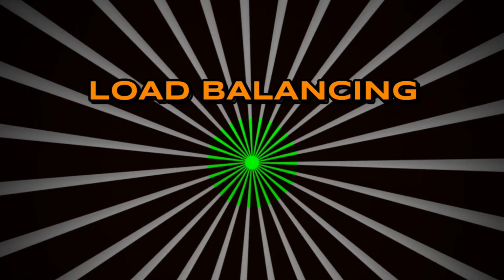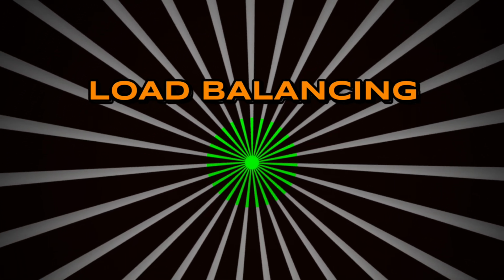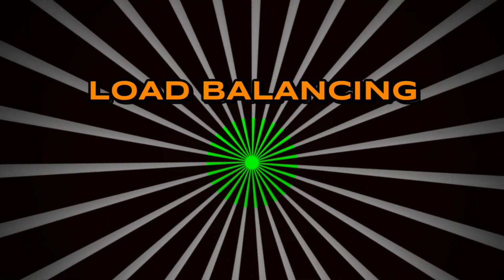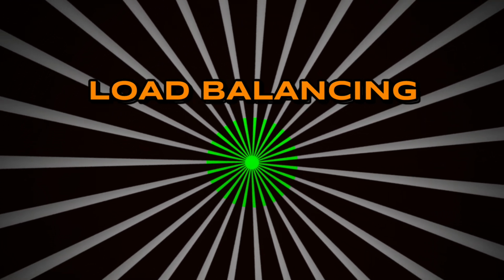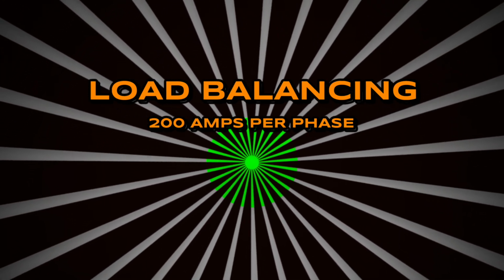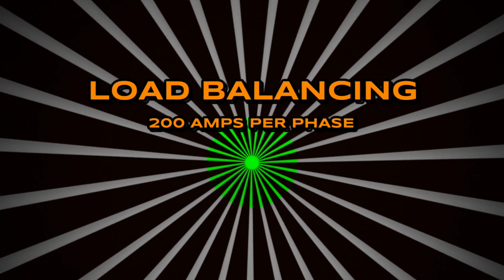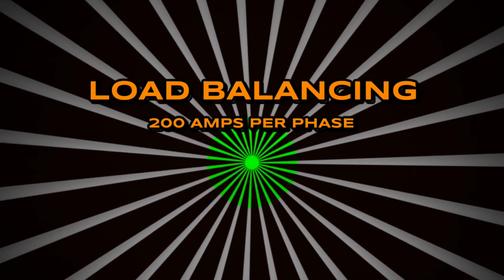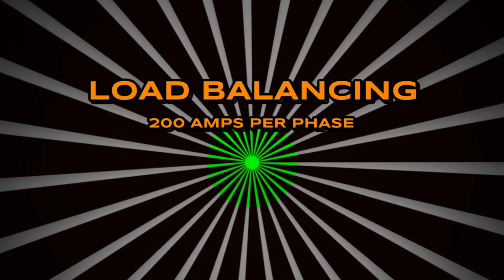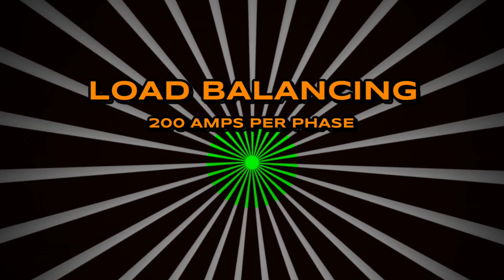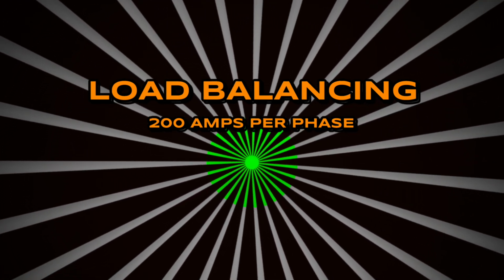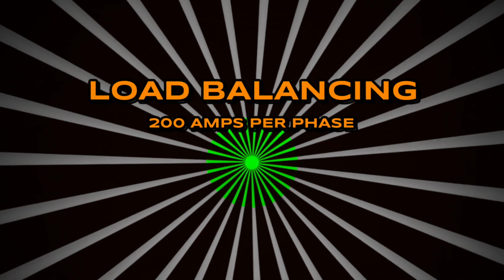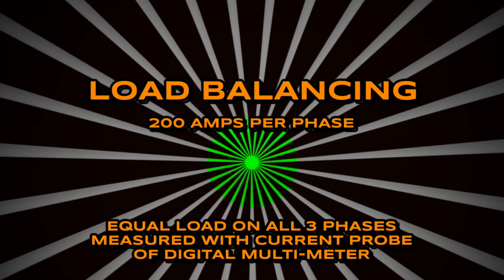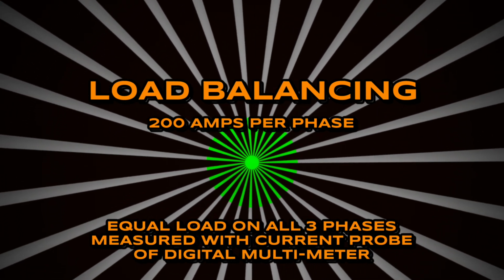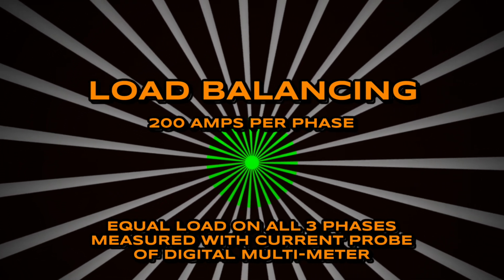Next up, load balancing. Well, what is load balancing? The 3 phases will all have the same current rating. With audio crews carrying 2-aught cable, they are capable of drawing 200 amps per phase. Usually at the start of a tour, you would plug in your electronics in a manner that you would expect to be doing the entire tour. And during production rehearsals or the first show, you would put a probe on each one of these phases. The goal is to draw equal current load on each one of these phases.